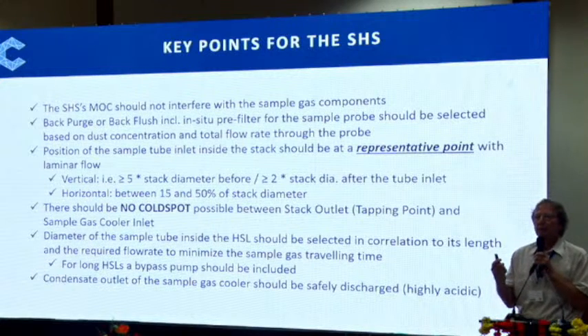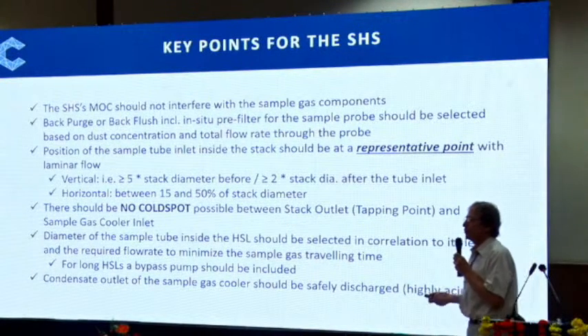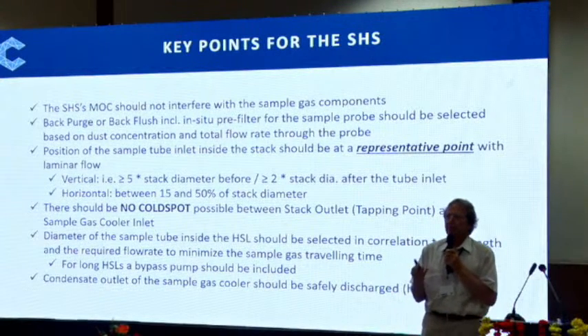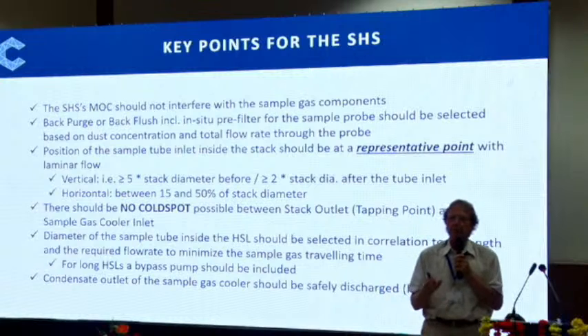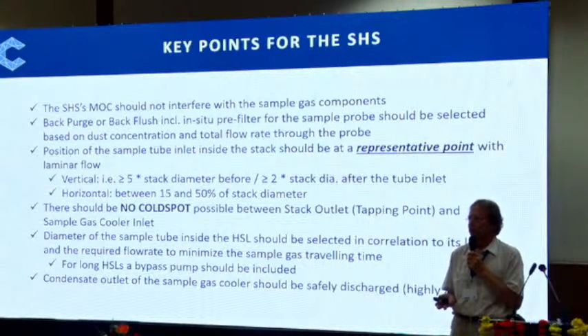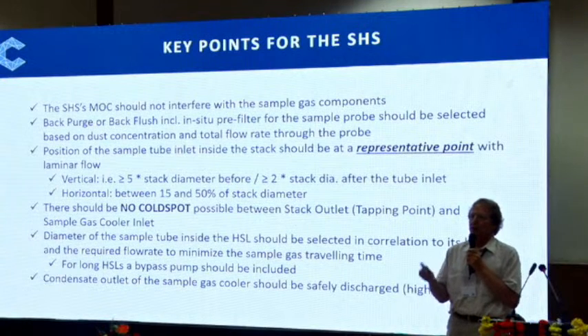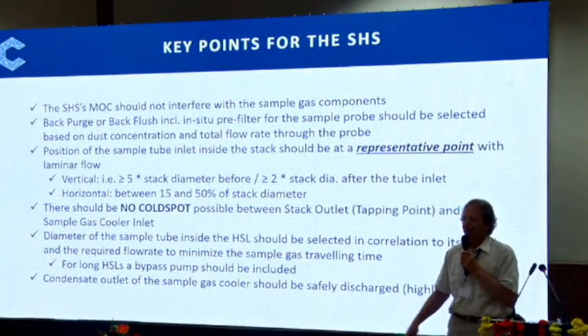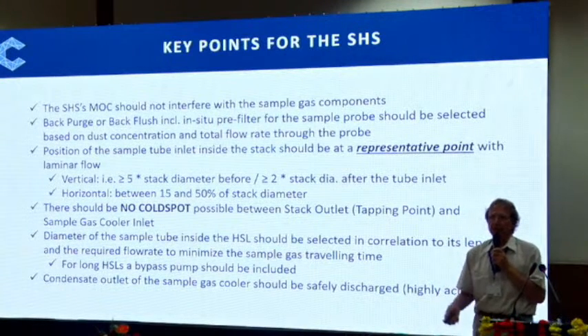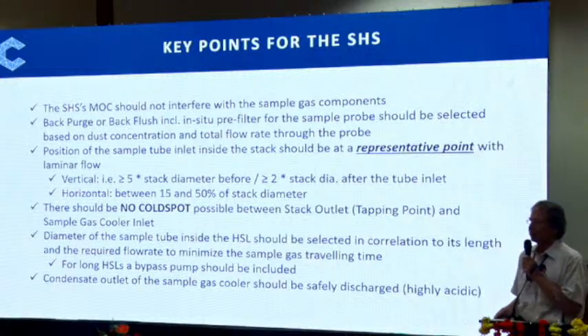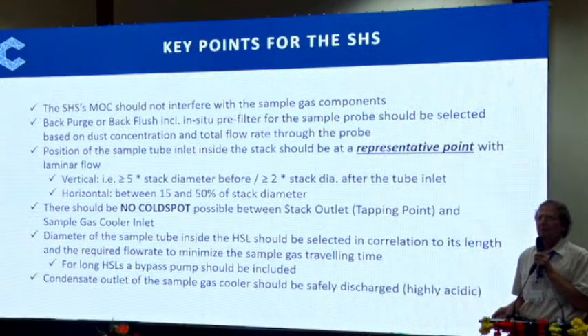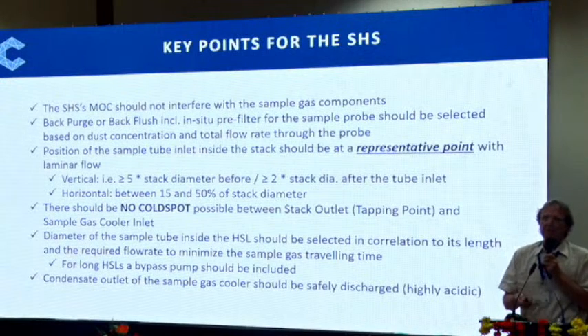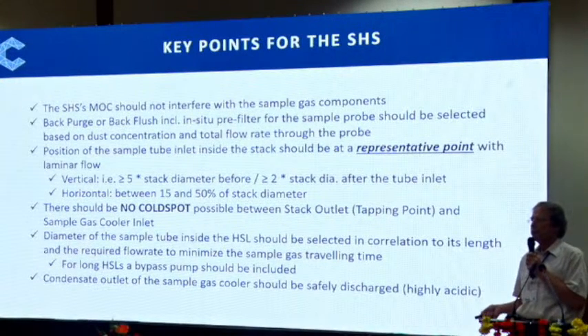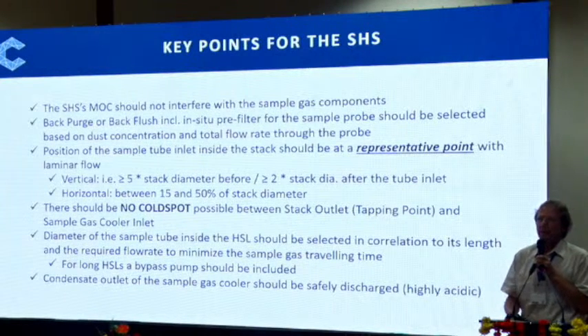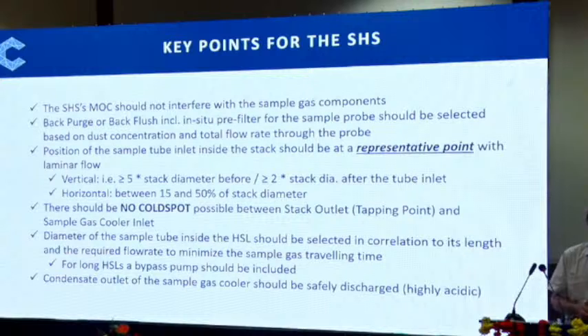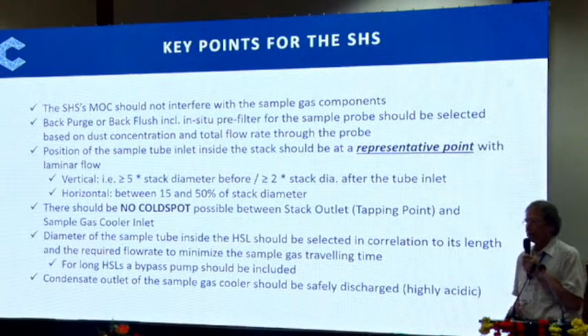And then there is an outlet, an effluent from the sample gas cooler. The effluent from the sample gas cooler is very acidic. We're talking about typically pH 1 to pH 2. Very acidic. So do not just let it drop out on the ground. Include it in the planned effluent, which is handled correctly. Why is it acidic? Because some components are water soluble, SO2, NO2, and they to some extent get dissolved in the condensed water in the heat exchangers. We're coming to that.